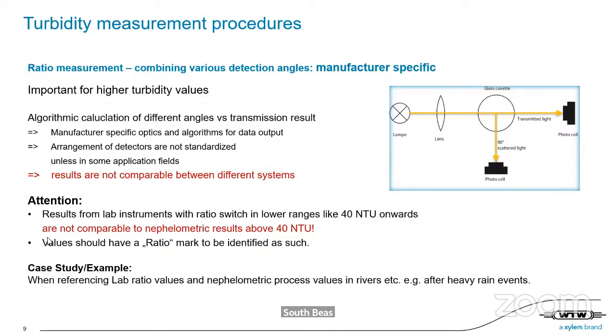And why is it important to know that? If you have a case study, for example, if you measure drinking water online or in a process, in a river or in a water reservoir, whatever, with higher values, and then you make a reference measurement, and you do have an instrument which doesn't read nephelometric but ratio above 40 NTU, nephelometric values from a sensor which is nephelometrically measuring is never the same as a lab instrument.